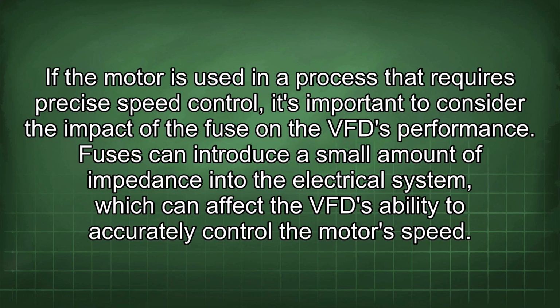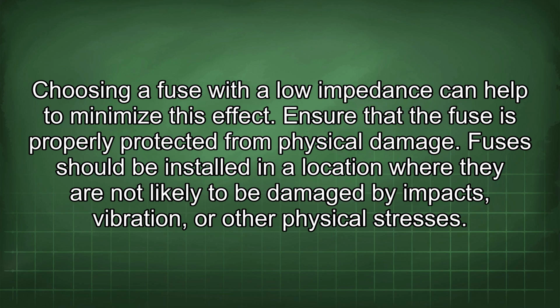If the motor is used in a process that requires precise speed control, it's important to consider the impact of the fuse on the VFD performance. Fuses can introduce a small amount of impedance into the electrical system, which can affect the VFD's ability to accurately control the motor speed. Choosing a fuse with a lower impedance can help to minimize this effect.